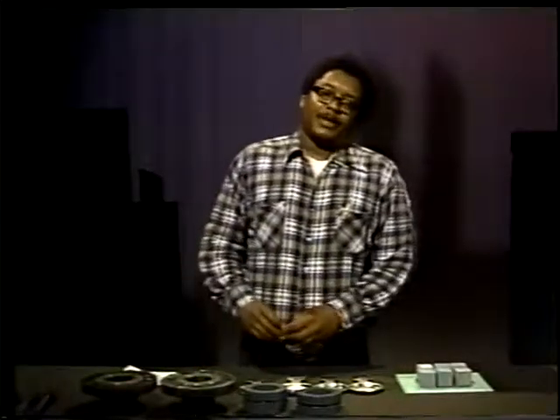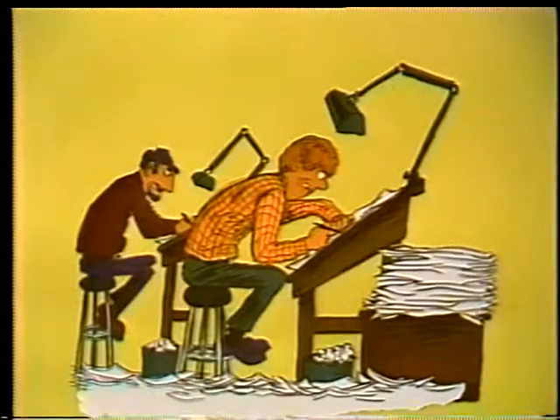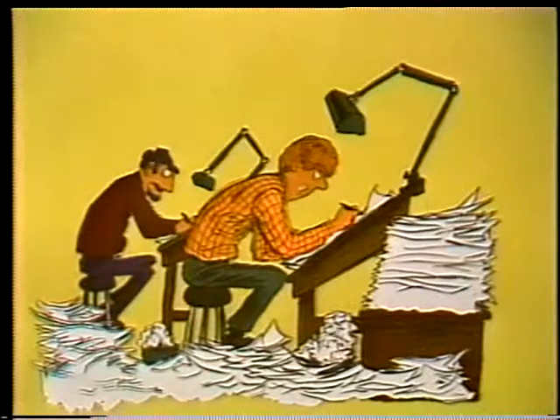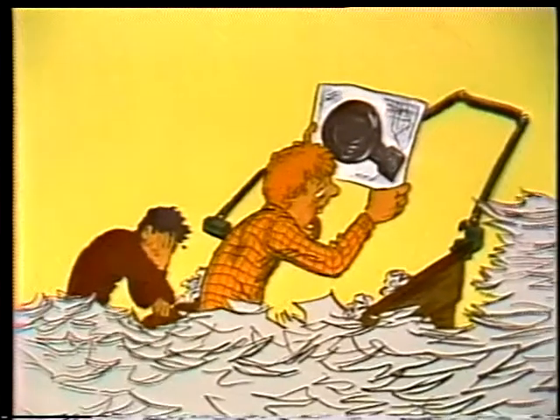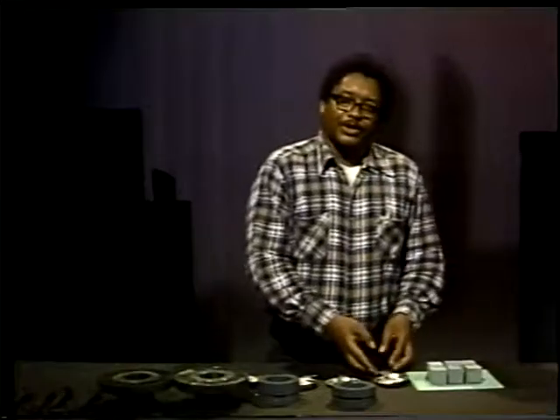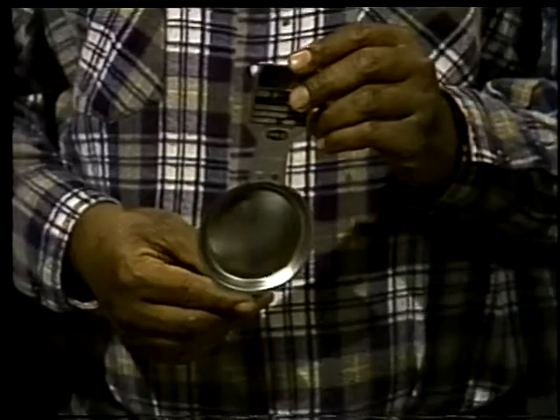And the rupture will occur at the weakest point in the system, the same way that a chain will break at its weakest link. To protect systems from damage caused by excessive pressure, designers and engineers look for a way to relieve excess pressure automatically and safely. The simplest design they came up with was the rupture disc. A rupture disc is a sheet of metal or other material designed to rupture at a predetermined pressure.